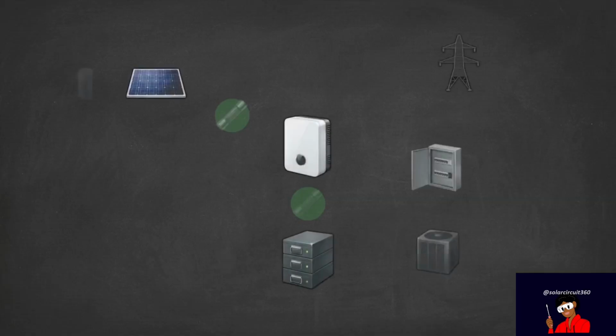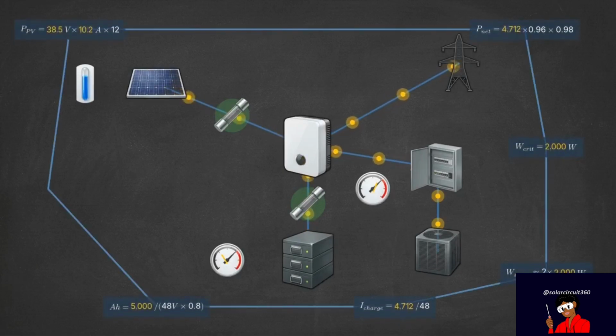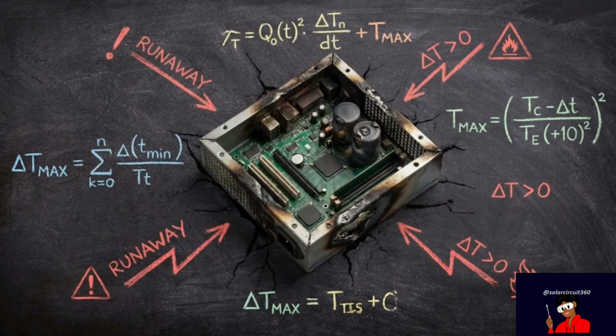This diagram shows the complete operational envelope. These 6 mathematical formulas interact simultaneously to maintain system stability. The hybrid inverter acts as an active management node, constantly balancing changing PV thermal variables, AC surge physics, and battery chemistry limits in real time. Breaching this mathematical envelope results in thermal runaway, equipment destruction, or electrical fires.